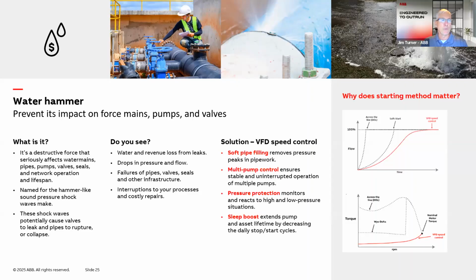This rapid surge in flow and pressure can damage the weak fittings, valve seals, and even rupture a pipe. You can often hear the destructive hammering noise it makes, and that's where it gets its name, water hammer. Now, if you apply a variable frequency drive to this pump, the VFD can be programmed to slowly ramp the pump up over time, maybe 20 or 30 seconds, to give a gradual increase in flow and pressure. The VFD can also be programmed to slow down the flow in a similar manner, eliminating water hammer for both starting and stopping the pump.